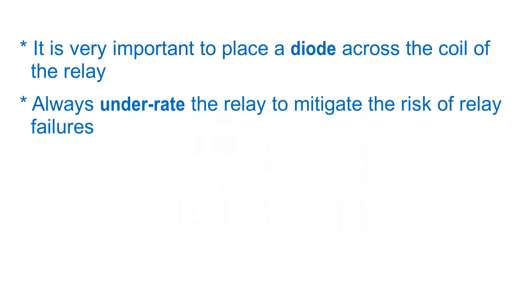Most importantly, same as capacitors, we always underrate the relay to mitigate the risk of relay failures. Let's say you need to work at 10 amperes at 120 volt AC. Don't use a relay rated for 10 ampere 120 volt AC.